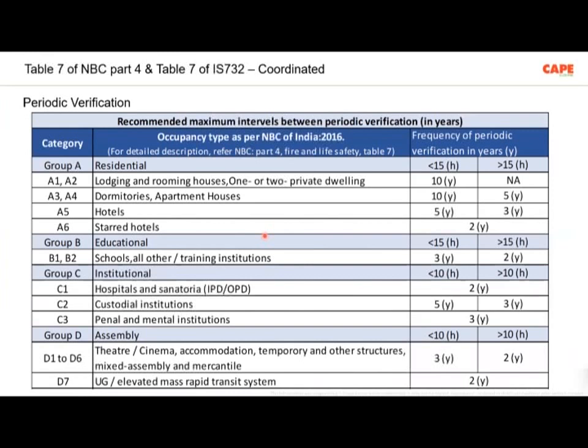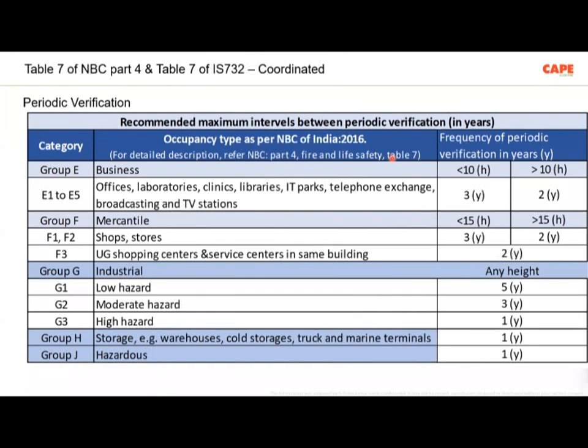There are two subjects which influence the building classification. One is what kind of special electrical installations are required in order to handle evacuation during an emergency. And the second one is the frequency of periodic verification. Regulation number 30 says the insulation resistance shall be tested every 5 years, but that is actually applicable to the electricity supply company. Whereas inside the electrical installation, this table has been included in the upcoming National Electrical Code. I think next month, probably before the National Electrical Code, BIS is coming out with a new standard, a guide for implementing electrical standards and regulations. So this guide also includes the tables which I am showing. Basically, the building classification and the periodic verification have been incorporated in line with the National Building Code.